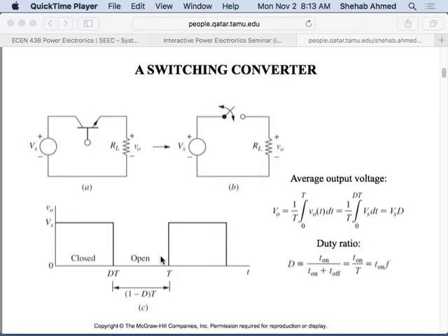But in certain cases, for example, where motors are connected to inverters or to power electronic devices through a long feeder, the motor is very distant from the power converter. Then, in these cases, we require filters. Why do we require filters? Because have you studied transmission line effects in 322, or no transmission line effects? Communication transmission line. You have not studied those. Okay.